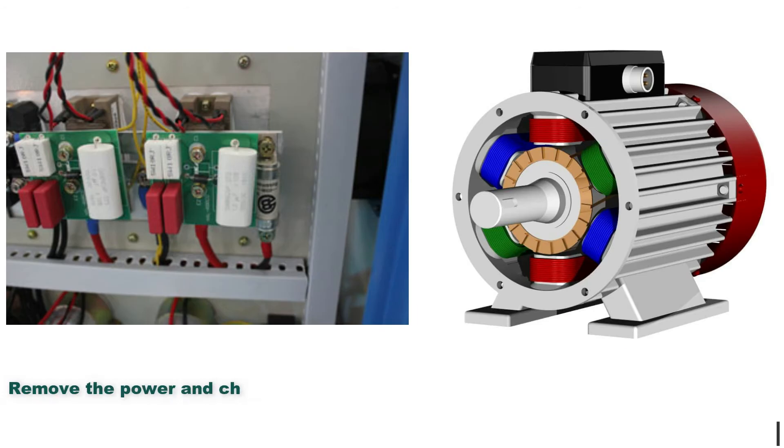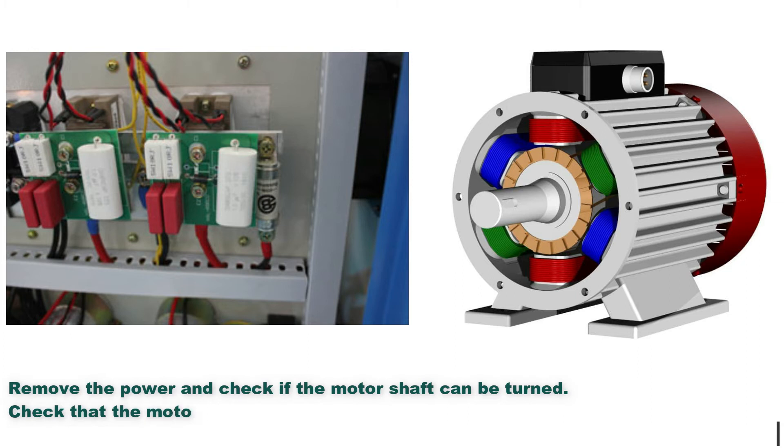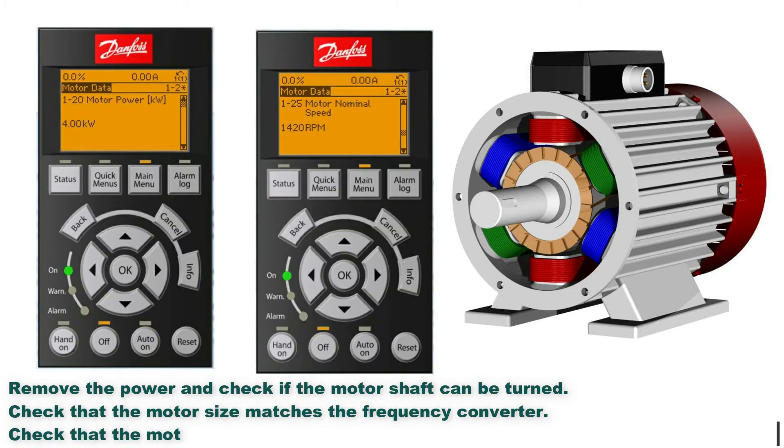Troubleshooting methods: Remove the power and check if the motor shaft can be turned. Check that the motor size matches the frequency converter. Check that the motor data is correct in parameters 1-20 to 1-25.